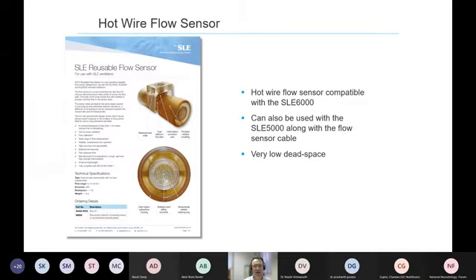If I just move on a bit, a technological step forward came a good 20 years ago with the development of these patient end flow sensors. When I say patient end, it means that the flow sensor sits proximally to the patient, right next to the mouth on the end of the breathing circuit. These flow sensors are of a very small volume. The dead space in here is less than 1 milliliter, meaning that they're perfect for neonatal ventilation in so much as they don't trap any CO2, which could subsequently be rebreathed.